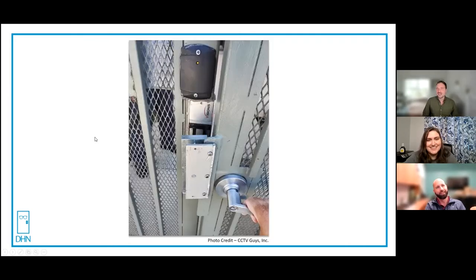Wow. Just wow. It almost takes your breath away. Well, first and foremost, what jumps out at me here is I don't even think that maglock I'm looking at is by definition one that's intended for outdoor use, from what I'm seeing right now. That's the first thing that comes to mind. I'll tell you right now, from just annual returns that we deal with, corrosion for those reasons is one of the biggest things we deal with as a company. So I would be worried that somebody's going to have to frequently repair something like this, let alone the fact that there are a lot easier ways, whether it's an electrified keypad lock on the actual side of the door, or an electric strike, that are a lot cleaner to achieve a similar result for what they're trying to do here.